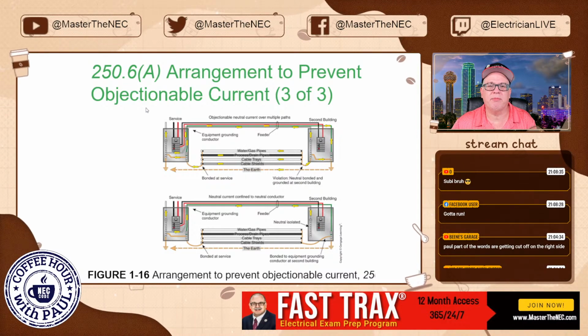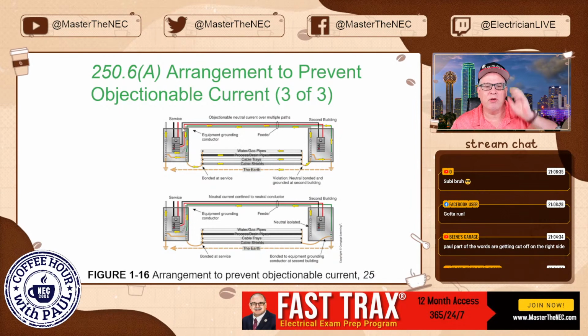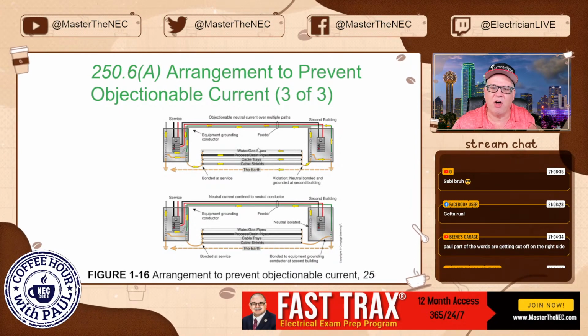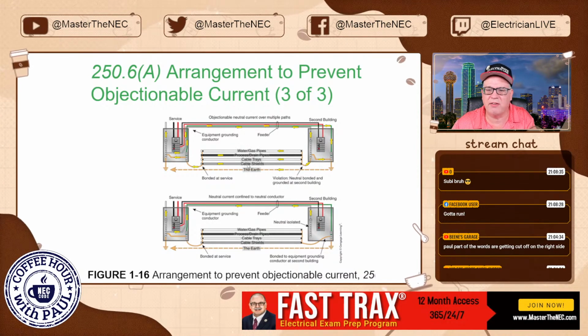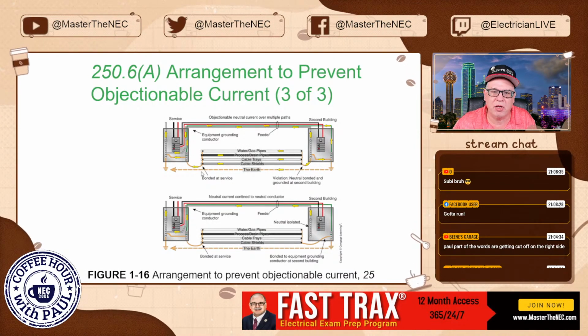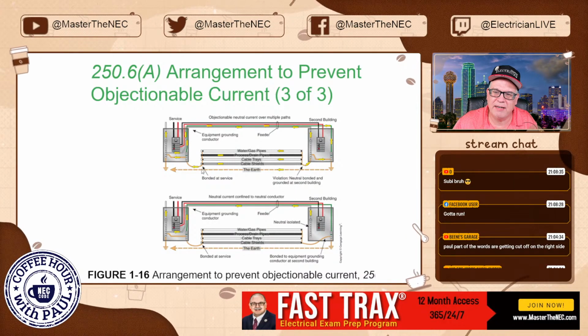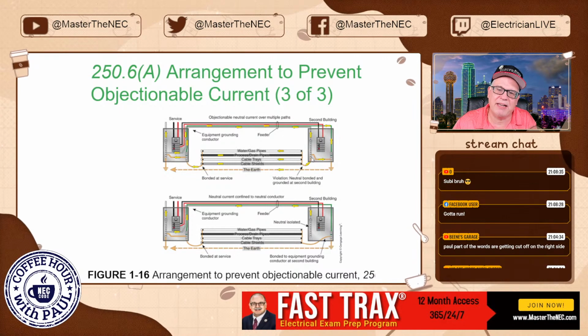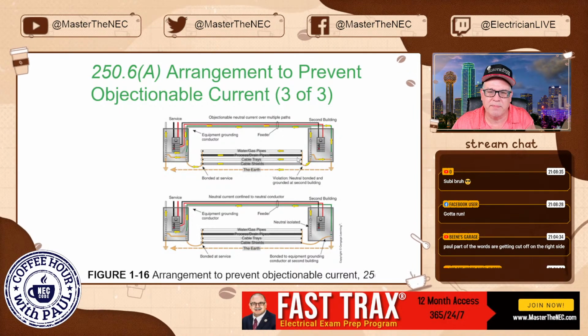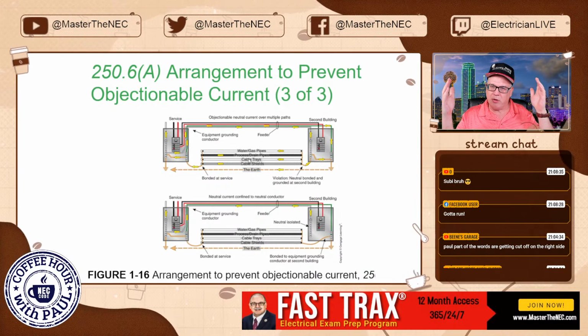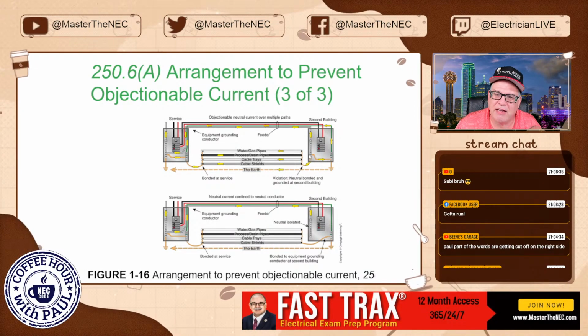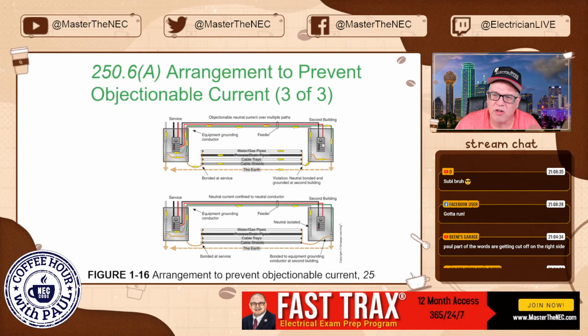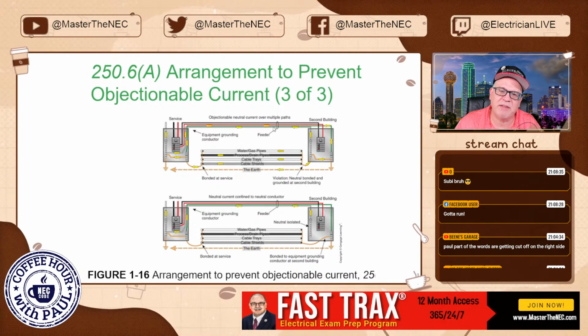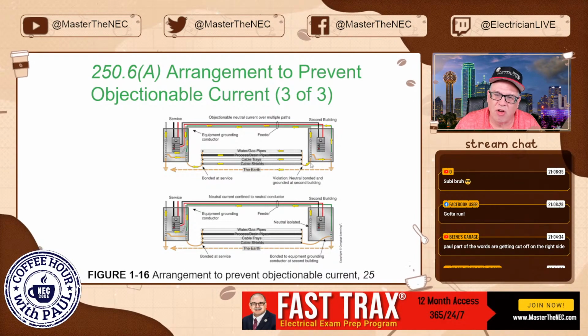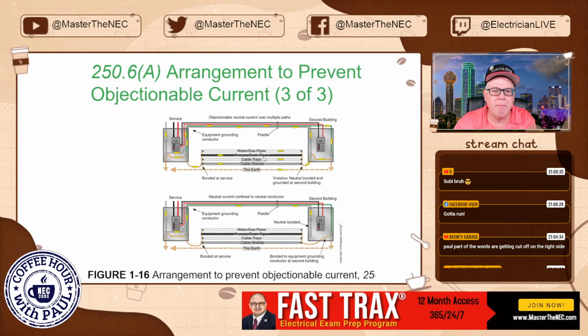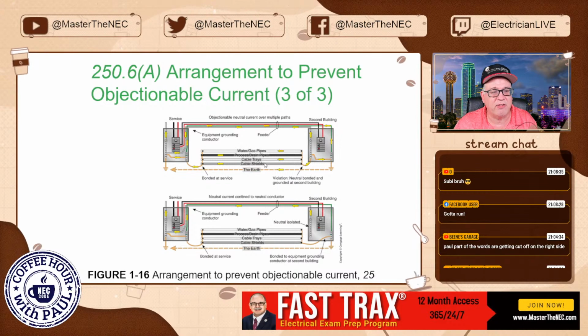250.6(A), arrangement to prevent objectionable current. So check this out. So this one up here, you have the service and you have a second building. Now you notice you have all of these gas lines, water lines, cable trays, cable shields, whatever, and it's mutual between buildings. So these are bonded at the service, right? But downstream, somebody improperly connects them to the neutral conductor. If these types of systems are mutual between the buildings, right? And then what you have now is neutral current traveling from the service to the second building, and instead of coming specifically back on the neutral's return path, it's also coming back on what? These other metal components. And this creates an example of objectionable current.